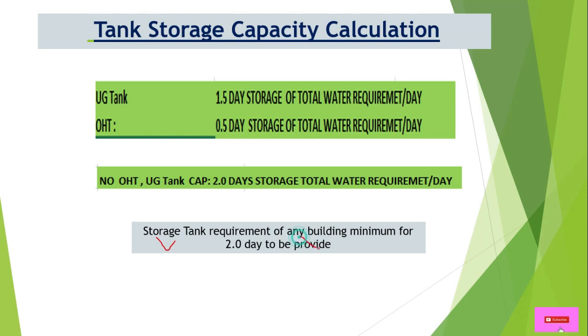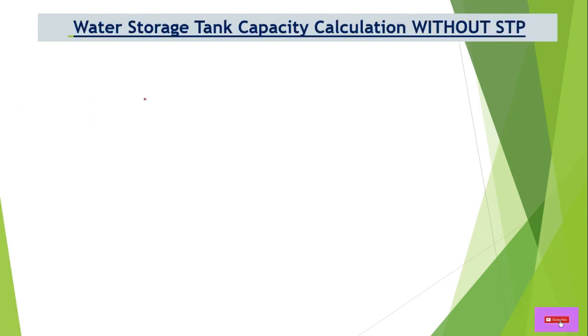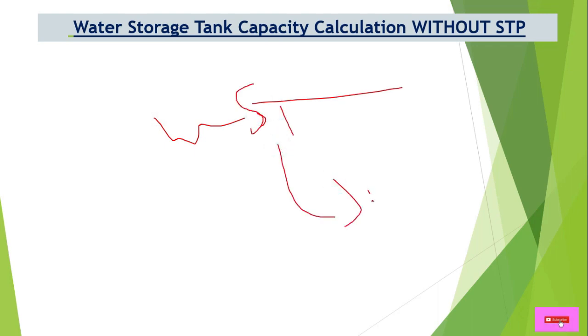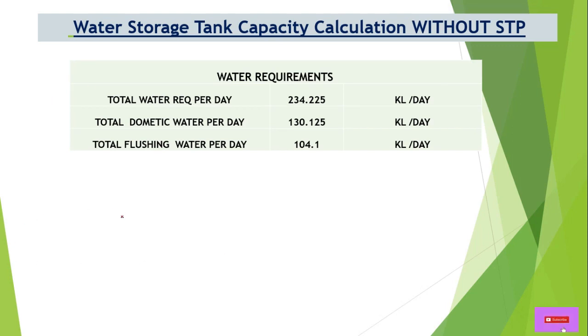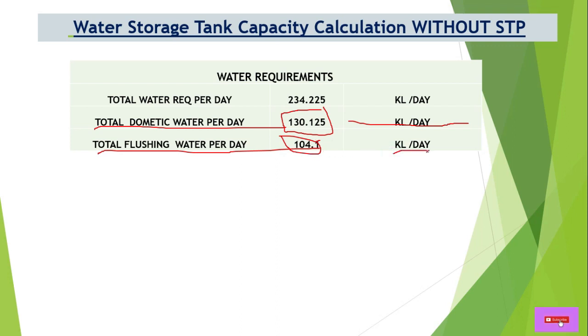We will calculate the water storage tank capacity both without STP and with STP. STP means Sewage Treatment Plant. Without STP means all wastewater is discharged to the municipal drainage — we will not reuse any wastewater. From our previous video, total domestic water supply is 130.125 KL per day, flushing water is 104.1 KL per day, and total is 234.225 KL per day.